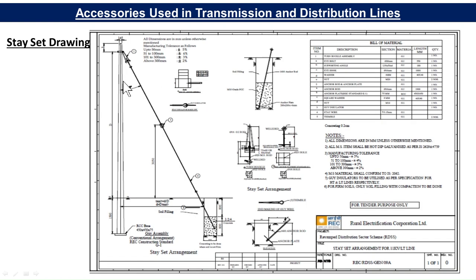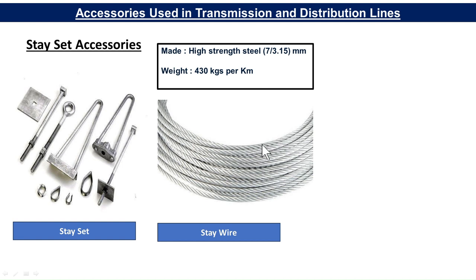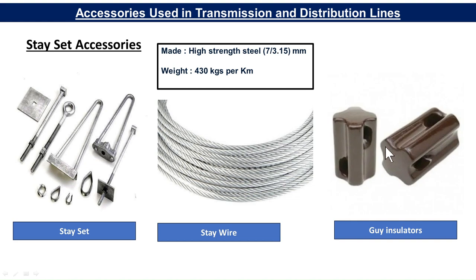These are the accessories of the guy stay set. The stay wire is made of high-strength steel, 7 × 3.15 mm, with a weight of 430 kg per kilometer. The stay set includes the guy insulator and various other components. All the different parts of the stay set are shown here.